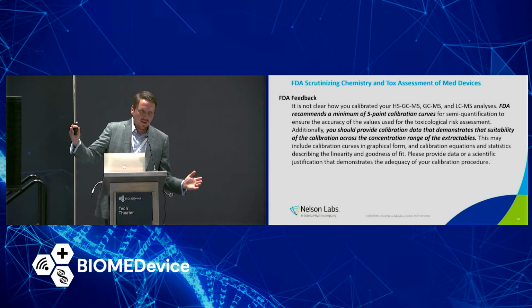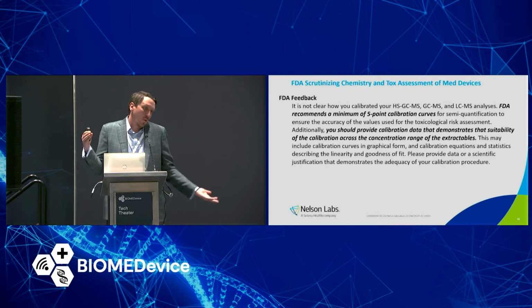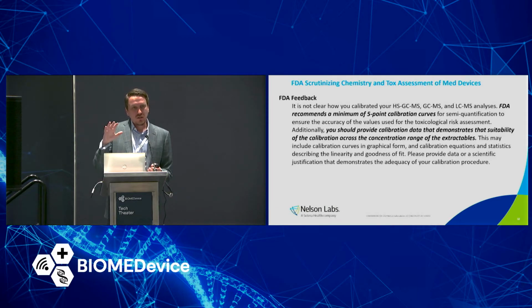The calibration curve has at least 5 points, and the range of that curve goes down low enough to measure the AET. And those surrogates should have a range of properties so that you could argue that we have a plasticizer, we have this thing, and that means that nothing's really falling off the charts here. And so for each method, there should be a minimum of those surrogates where this criteria is met. And that's how it looks at most labs today. And if the FDA asks, they can give you this list of surrogates and this linearity and all this other stuff. So this is something that is newer and important, and it's something that the lab should be ready to provide.